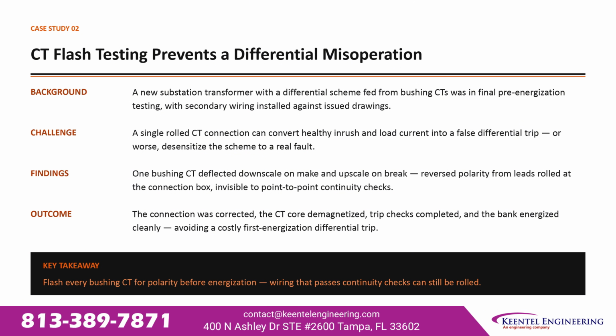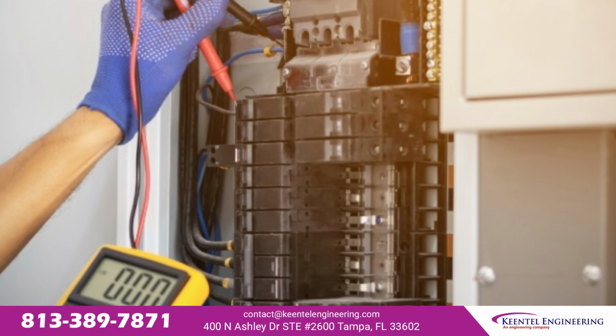One bushing CT deflected downscale on make and upscale on break, reversed polarity from leads rolled at the connection box, invisible to point-to-point continuity checks. The connection was corrected, the CT core demagnetized, trip checks completed, and the bank energized cleanly, avoiding a costly first energization differential trip. The takeaway: flash every bushing CT for polarity before energization. Wiring that passes continuity checks can still be rolled.